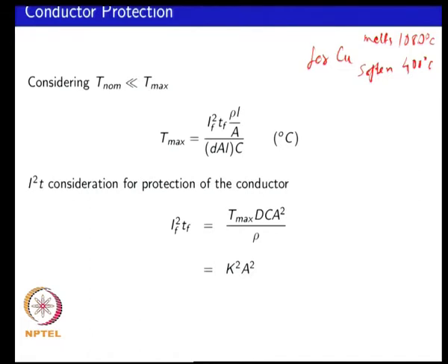If you look at the insulation, your PVC insulation will start getting damaged at 160 degrees centigrade. And if you look at more sophisticated insulation such as XLP or cross linked polyethylene, you are talking about maybe 250 degrees C.